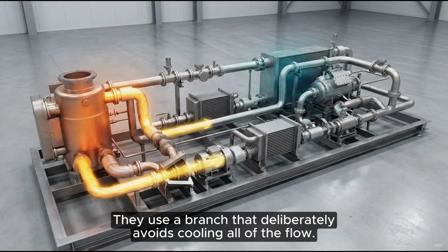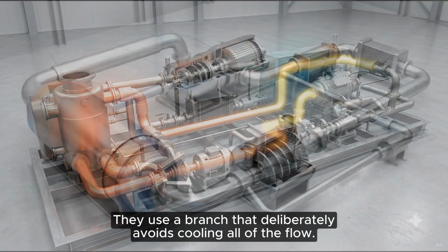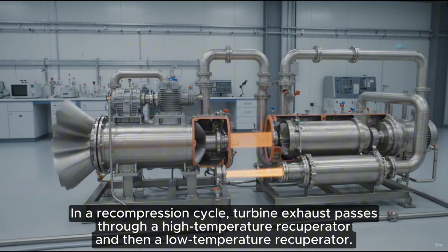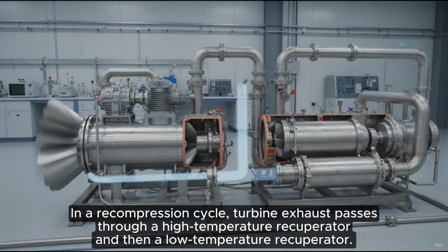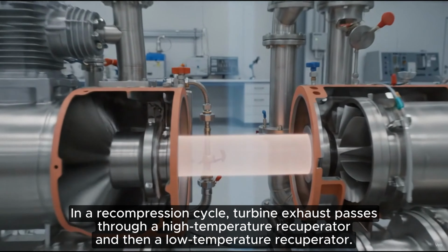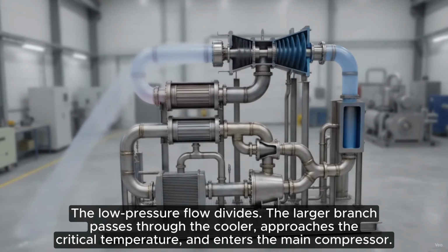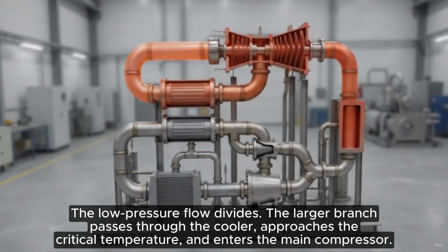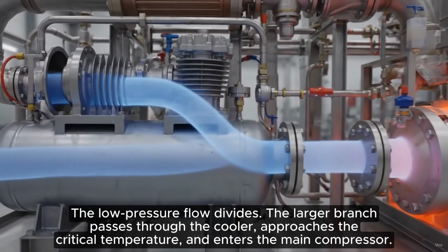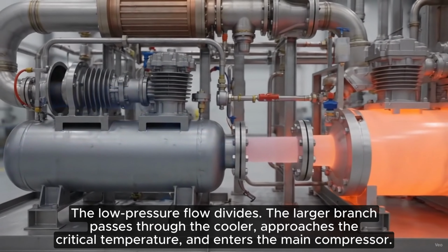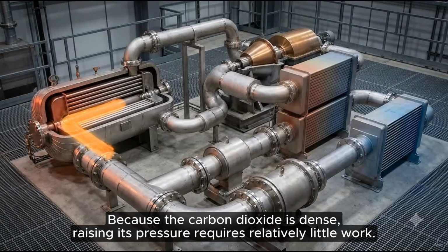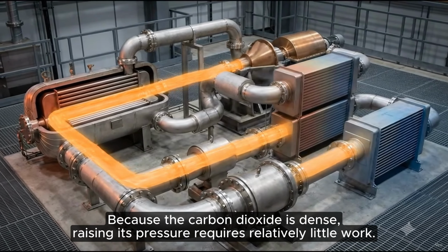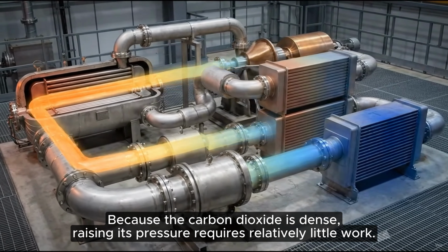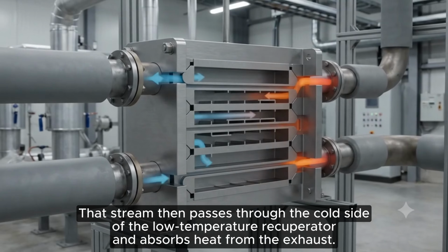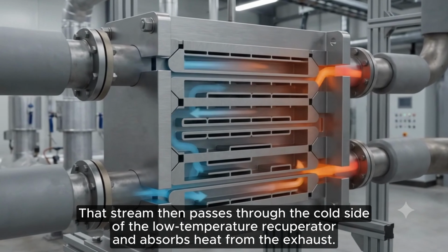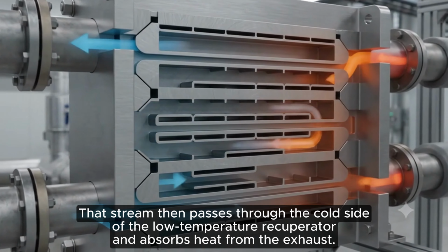They use a branch that deliberately avoids cooling all of the flow. In a recompression cycle, turbine exhaust passes through a high-temperature recuperator, and then a low-temperature recuperator. The low-pressure flow divides. The larger branch passes through the cooler, approaches the critical temperature, and enters the main compressor. Because the carbon dioxide is dense, raising its pressure requires relatively little work. That stream then passes through the cold side of the low-temperature recuperator and absorbs heat from the exhaust.